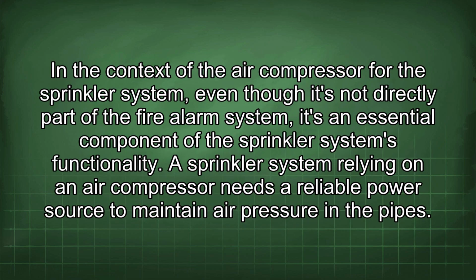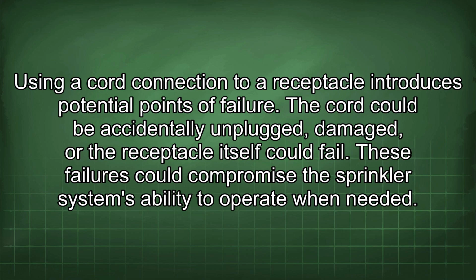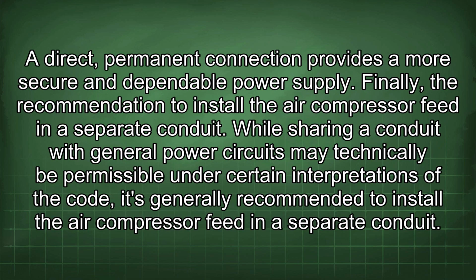In the context of the air compressor for the sprinkler system, even though it's not directly part of the fire alarm system, it's an essential component of the sprinkler system's functionality. A sprinkler system relying on an air compressor needs a reliable power source to maintain air pressure in the pipes. Using a cord connection to a receptacle introduces potential points of failure. The cord could be accidentally unplugged, damaged, or the receptacle itself could fail. These failures could compromise the sprinkler system's ability to operate when needed. A direct, permanent connection provides a more secure and dependable power supply.